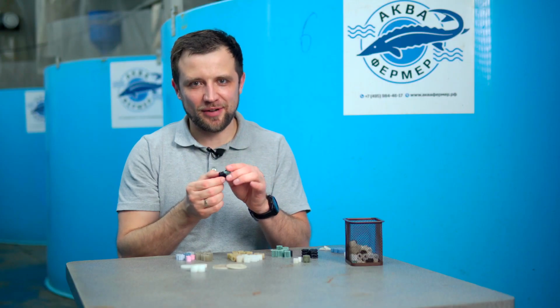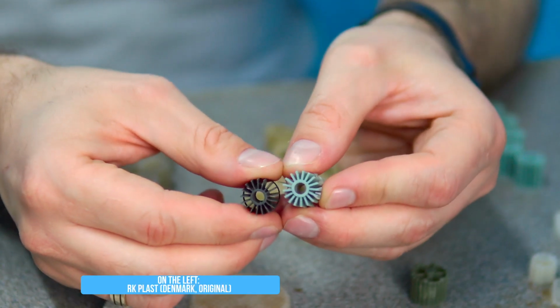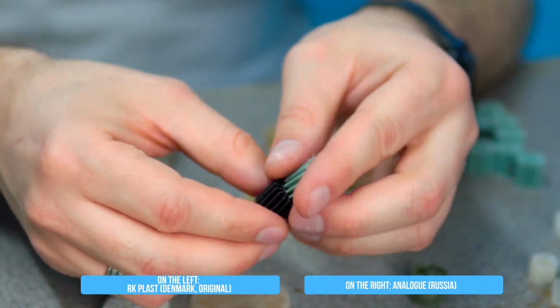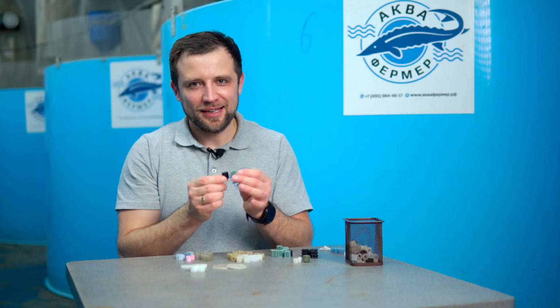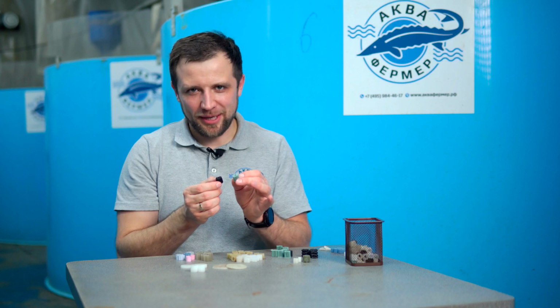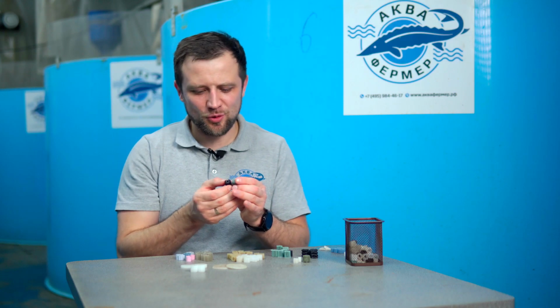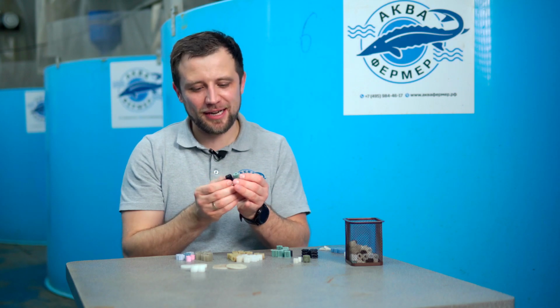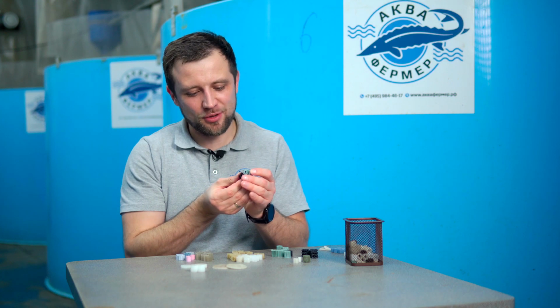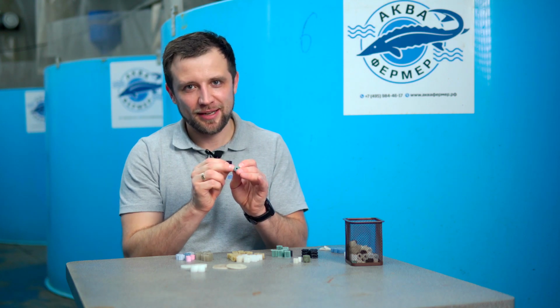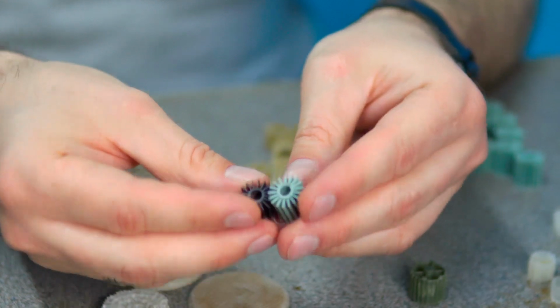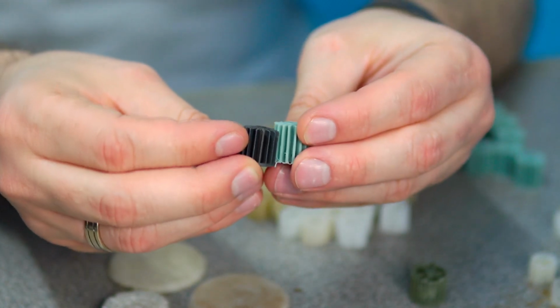Let's compare these 2 types of media. This is the Danish original media. This is the Russian counterfeit. This media is almost the same size, the same quantity per cubic meter, even the number of ribs is the same. But there is one significant nuance: Russian media cannot make such thin ribs as on the Danish one. And here the ribs are thick.